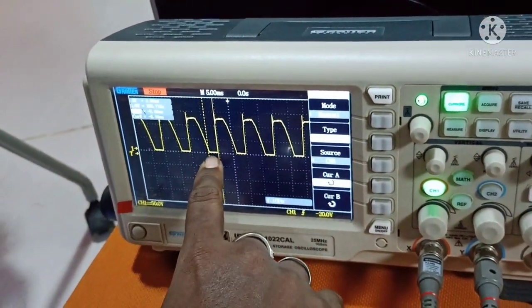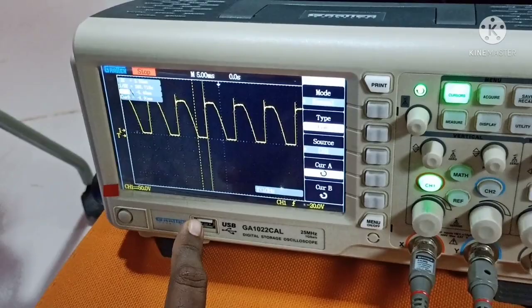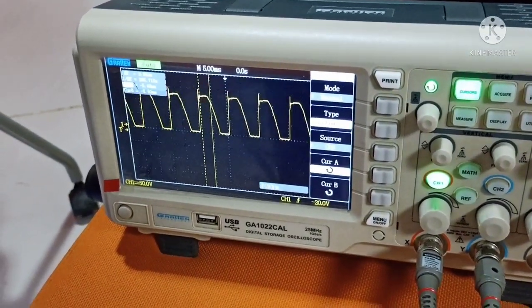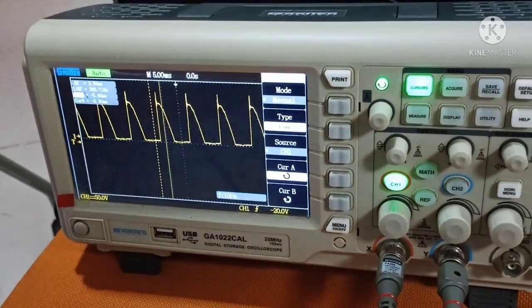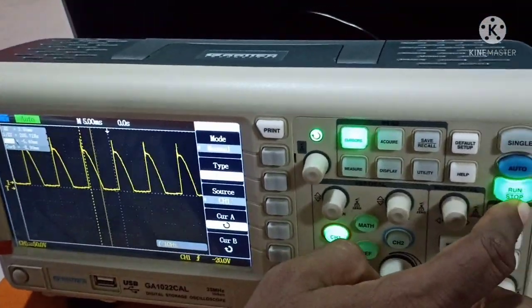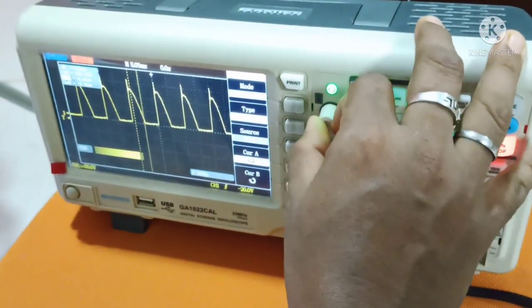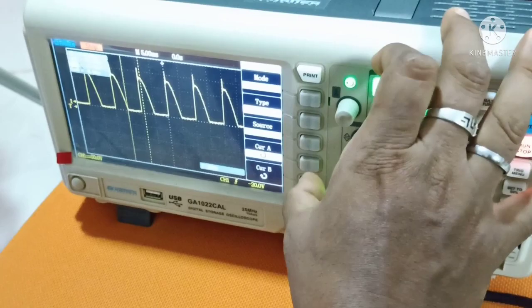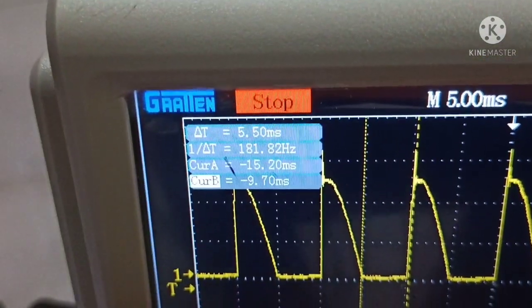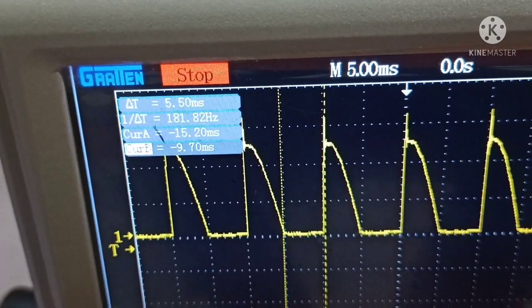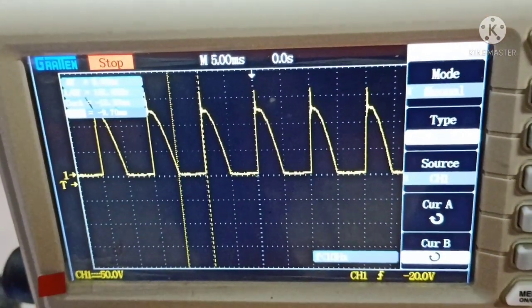This 3.5 milliseconds can be converted into the firing angle using the standard equation. Let us now change the firing angle by updating the value in the program. After updating, you can see that the firing angle has changed. Measuring again with the cursor function shows approximately 5.50 milliseconds has been blocked. The firing angle can be calculated by converting time into angle.